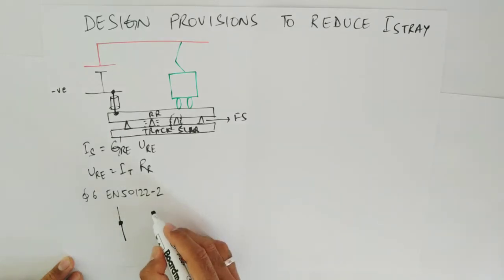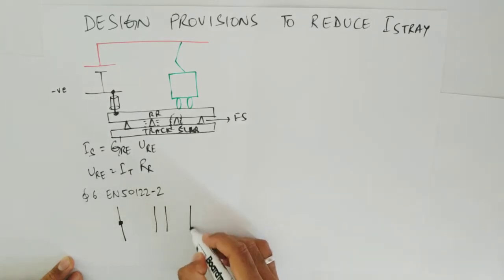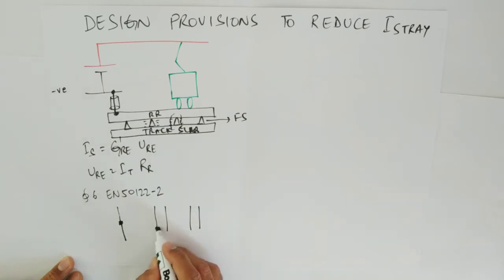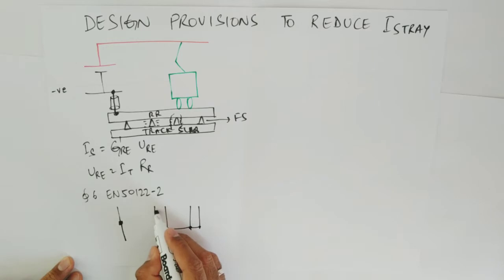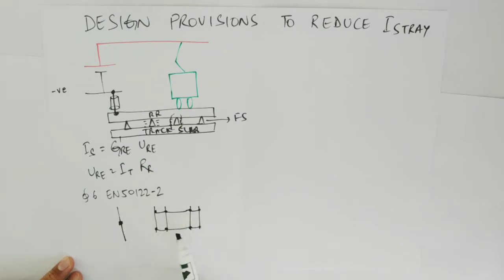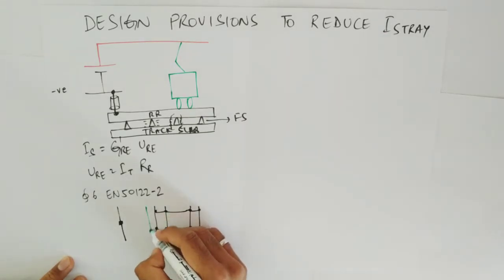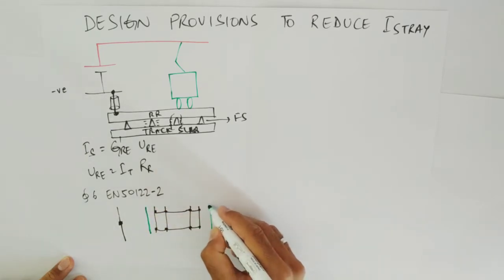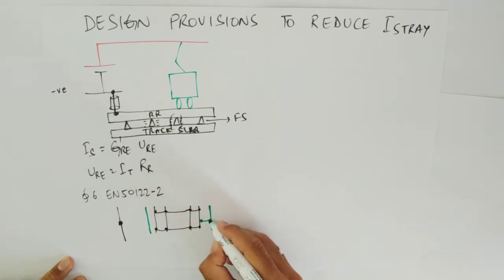Apart from this, suppose this is your up track and this is your down track. We provide cross bonds — that is between track to track and rail to rail. These cross bonds reduce the effective resistance by making the running rails parallel. Even after this, if we are not able to achieve the required values, we provide an extra conductor known as the return conductor, which is connected to these running rails.